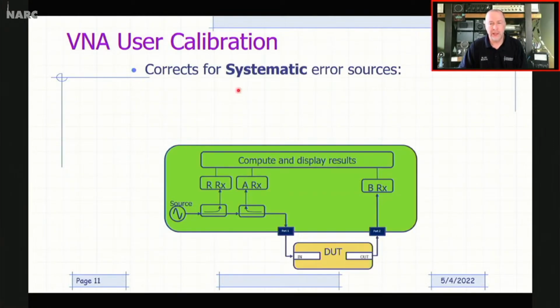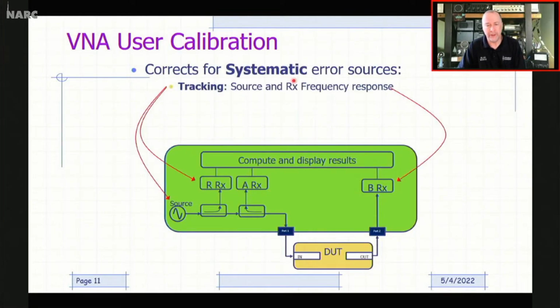So again, the calibration corrects for systematic error sources. And these are things such as tracking errors. Tracking errors refer to the source and receiver frequency responses. They're not going to be perfect. The magnitude and phase response of these amplifiers and measurement receivers are not going to be perfect. The amplitude over frequency of the source isn't going to be perfect. So we measure that and then are able to mathematically remove that from our measurements.